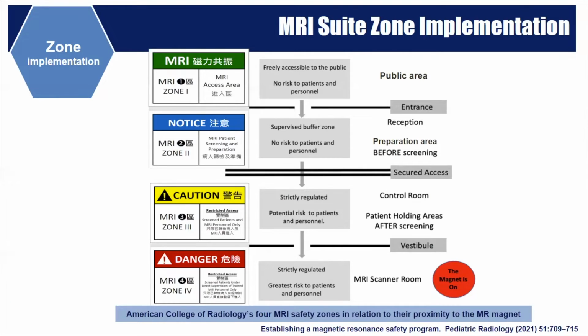Once MR is installed and our magnet was ramped up, we implemented zoning. MRI suite is divided into 4 zones. Zone 1 is MR access area, which is a public area. Zone 2 is MRI patient screening and preparation area. Zone 3 is a restricted access area, which is a control room. And Zone 4 is restricted access area, which is the magnet room.